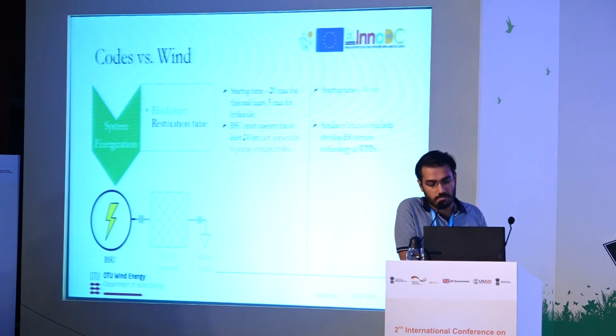But one important thing is that Blackstart units are required to maintain operation for at least 24 hours after having started. This is not applicable for pump storage hydro, because you would not want to exhaust the water in the upper forebay; if another blackout occurs, you need to have another service possible. So some sort of similar relaxation in grid codes, which some TSOs in Europe that I met can provide. For example, instead of 24 hours, they could allow only 8 hours of operation as a minimum requirement. But what's important is to use this large amount of power from the wind in the initial stages of the restoration procedure.